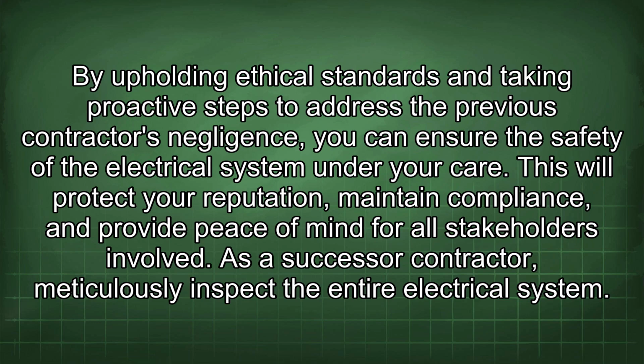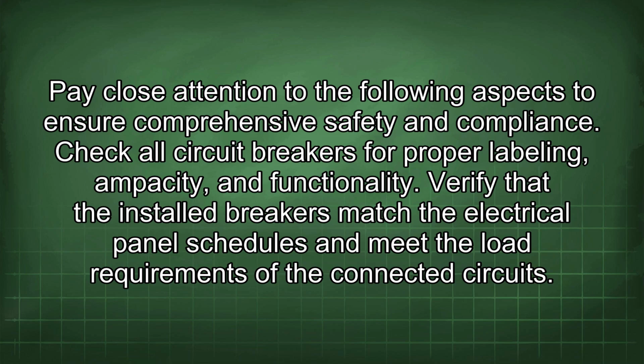As a successor contractor, meticulously inspect the entire electrical system. Pay close attention to the following aspects to ensure comprehensive safety and compliance. Check all circuit breakers for proper labeling, ampacity, and functionality. Verify that the installed breakers match the electrical panel schedules and meet the load requirements of the connected circuits.